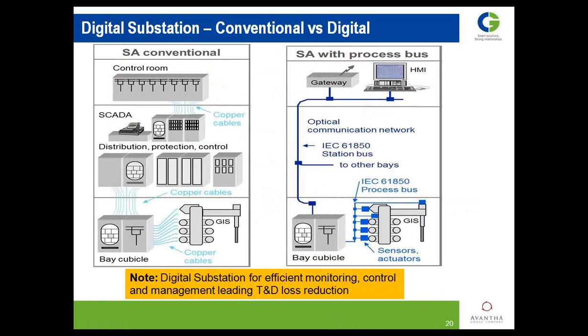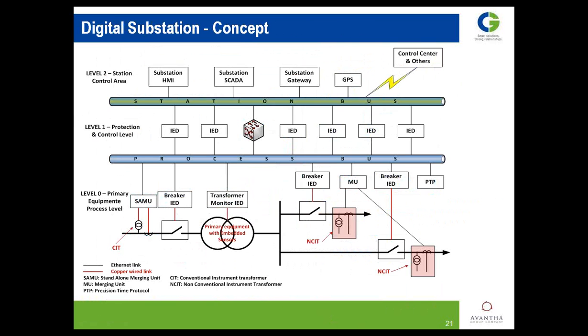I have better and better field level monitoring, and that is getting reflected towards the control room. And for the overall system, as per the need and requirement, I can monitor, I can control, and I can manage my system more efficiently and robustly. That's the concept of digital instead of a conventional analog one with a lot of copper wiring, higher cost, and a lot of probability of failure of the system with less redundancy, I will say. This is the concept of digital substation.